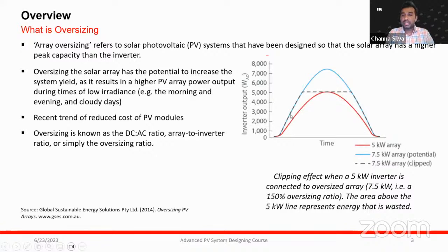In simple terms, the curve will be much widened, especially in morning hours and evening hours. The area underneath this power and time curve represents energy, meaning much higher energy yield early in the morning and later in the evening, with much higher solar potential. But since it's connected at much higher capacity, the inverter does provide a limitation - it won't go beyond 5 kVA, so it limits the power output from the inverter itself. In this case, some energy will be wasted, which we simply call power clipping. The power clipped energy represents this loss, but you get much more consistent power and energy throughout the day since you've already oversized the array to the inverter.